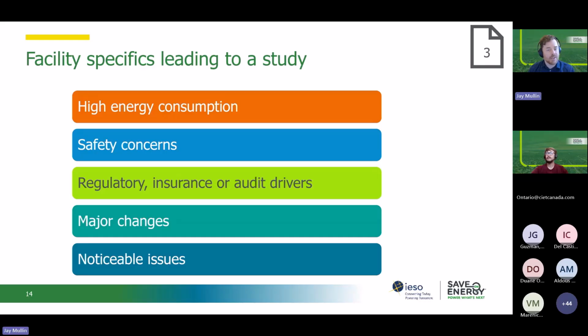First, if you have high energy consumption or high levels of exhaust and makeup air, it can be a good way to help save energy. There can be safety concerns around that, as I mentioned, fumes and exhaust backflows. It can be related to regulatory, insurance, or audit drivers, major changes to the facility, or if there are noticeable issues or symptoms related to pressurization happening in the facility.